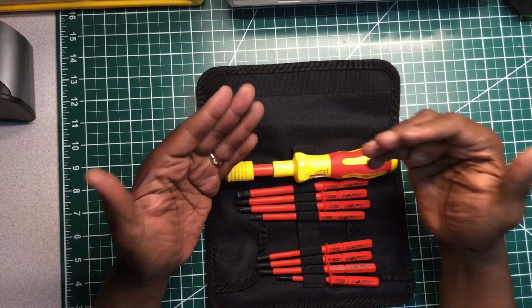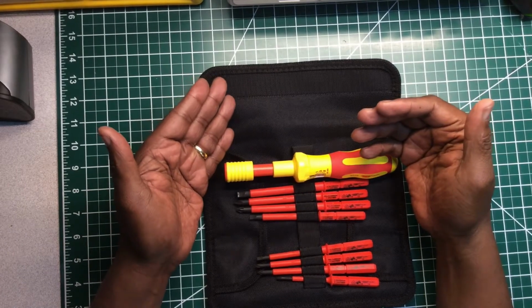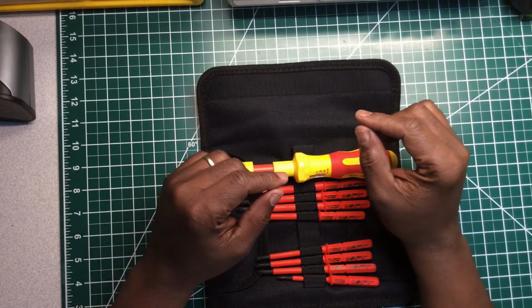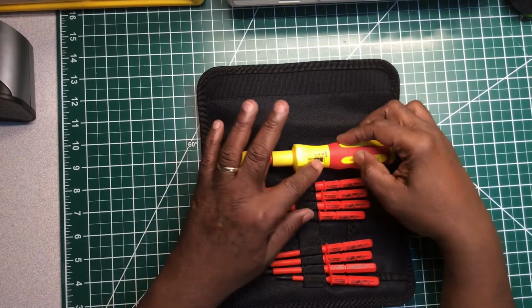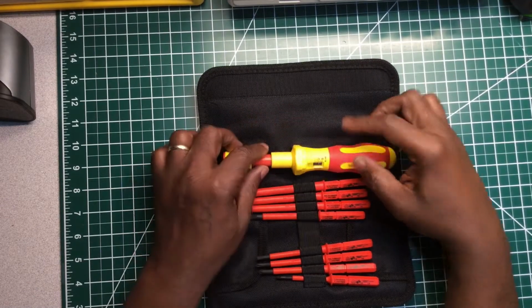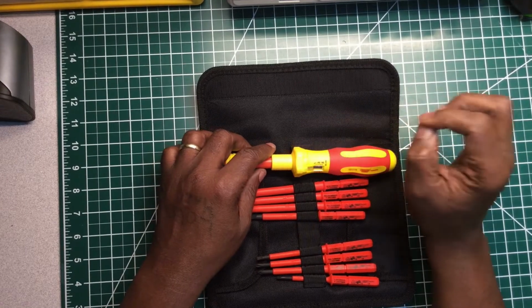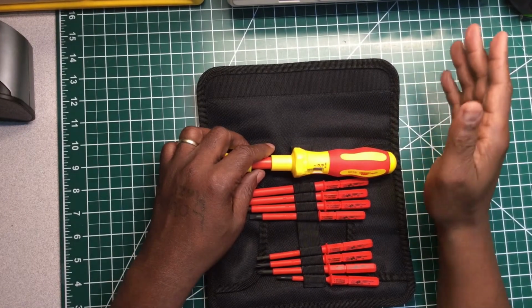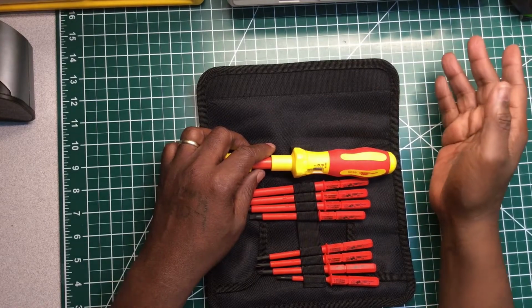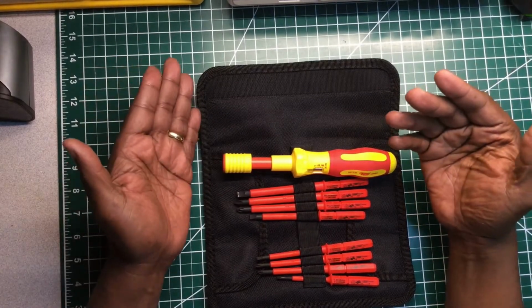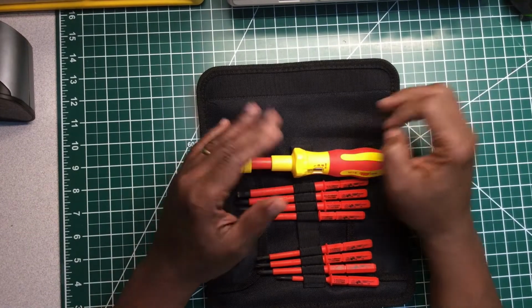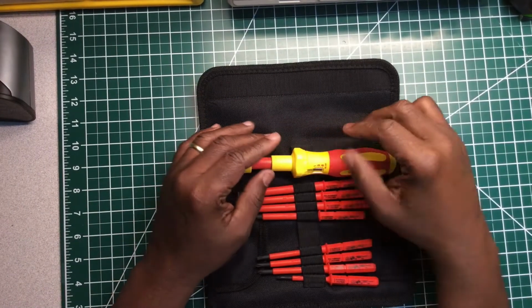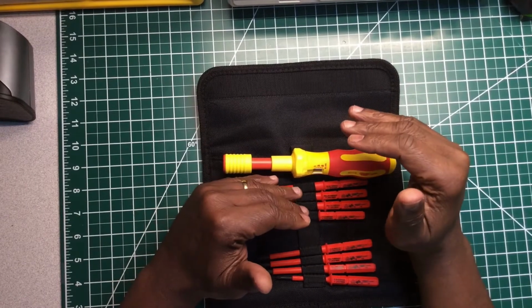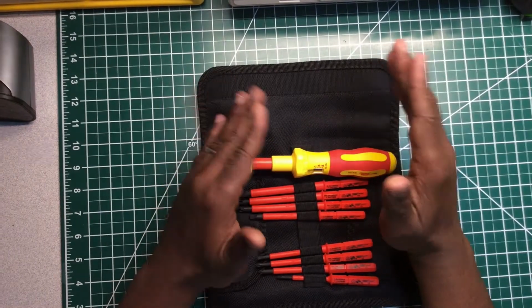Like I mentioned in my previous videos about my other torque screwdrivers, Square D breakers, not all of them, often call for 36 inch pounds, which would be 4 Newton meters on this screwdriver. Now the terminal bus bar may call for something else, maybe 40 inch pounds, and the ground, earth ground, may call for a different value. So don't just assume that because it's made by a certain company they all use just one certain value. That's not the case.